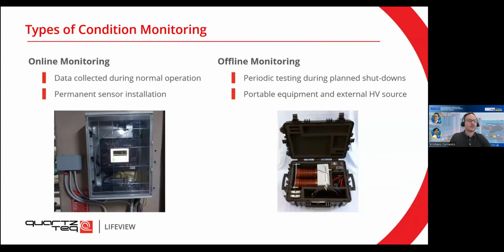As I mentioned briefly in one of my first slides, there are essentially two main types of condition monitoring. One is online, so data is collected during the normal operation of the machine. It needs the installation of sensors. The sensors are installed once the machine is off, but once it's back on, we can capture the data and analyze it. On the other hand, offline monitoring would be performed once the machine is off. This would happen periodically during planned shutdowns, and usually you would use portable equipment and an external high voltage source to do this type of condition monitoring. For offline and online monitoring, I'm also going to explain a bit of the differences and the pros and cons each of these types of monitoring has.